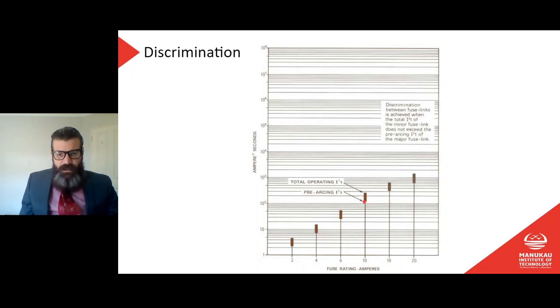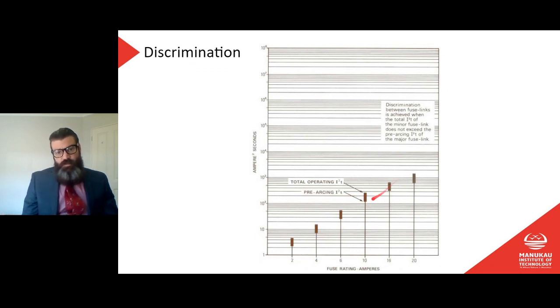So could we use a 16 as a backup to a 10? Yep, because for the 10 there, see the total operating I squared T is below that line, and for the 16, the pre-arcing is above that line, so that's fine. And then we would have good discrimination. And again, what does discrimination mean? That means that the lower one will trip before the higher one. There's no point having the 10 amp circuit breaker on our lighting circuit if the 20 amp circuit breaker that powers our whole house just keeps tripping all the time. If the 20 amp trips before the 10 amp, then it's a waste of time to have both of them, right?